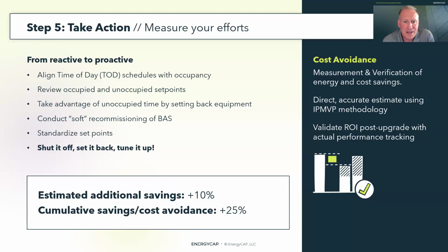So if you know you haven't done something in a building for 5 years, you haven't added equipment or done anything mechanical in the building, very likely that system is a little out of whack. Spend some time getting into the building automation system, looking at set points and airflows, just run some reports and do some analysis. And my guess is you're going to find the opportunity to save within those buildings.